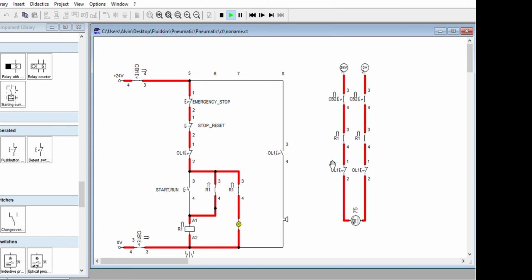Then what will happen here? This will react, of course not instantaneously. Remember, this will not trip by short circuit. This will trip on overload current, that is by increments, not instantaneous current. The change of overload current is not instantaneous but by increment. So let's say inside 1 minute or after 1 minute, some overload thermal elements will react depending on the setting. So again, maybe 20-25% more than the motor's full load current, that is 125% of the full load current, to set the thermal overload relay.